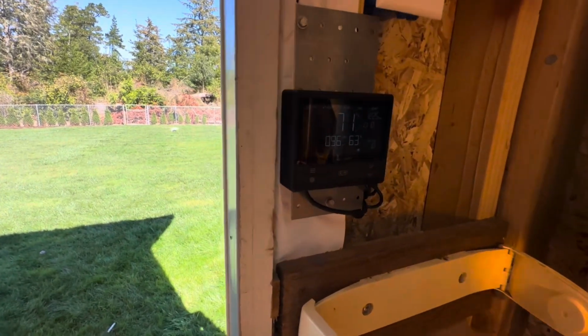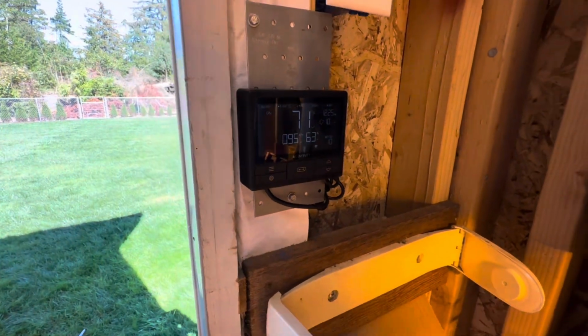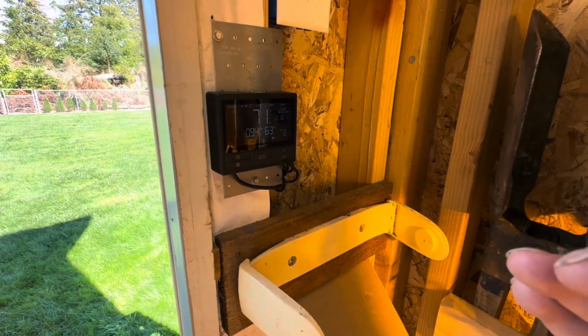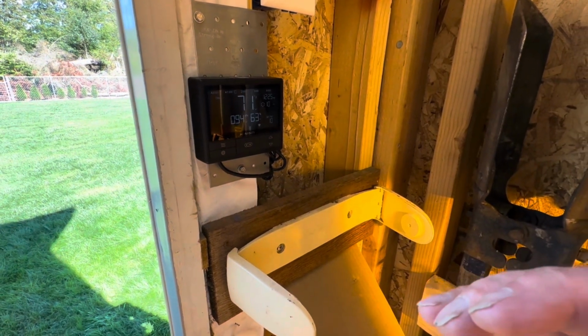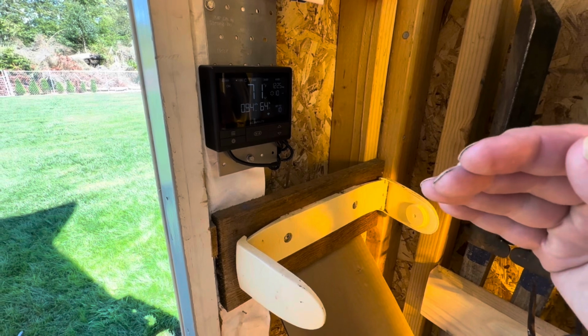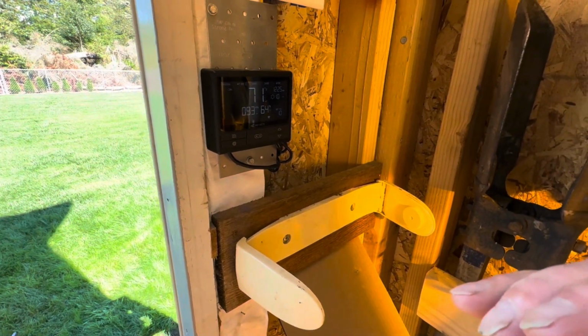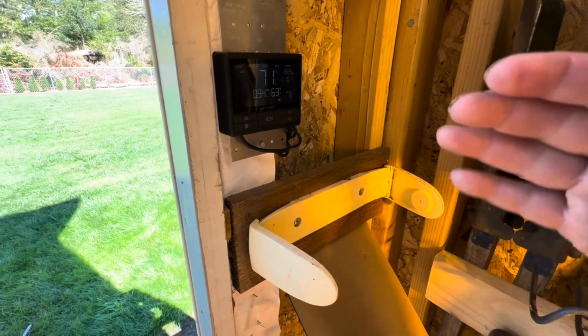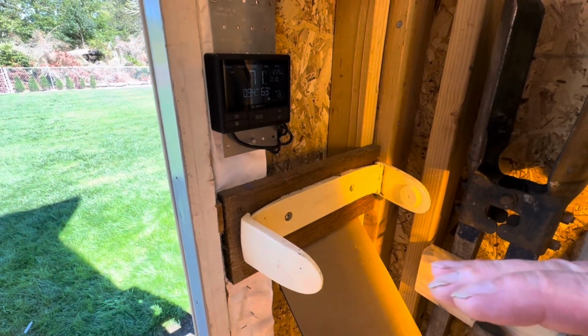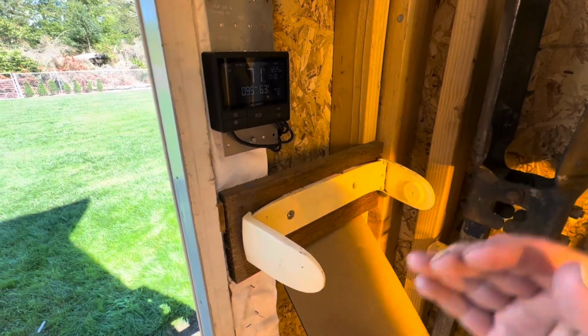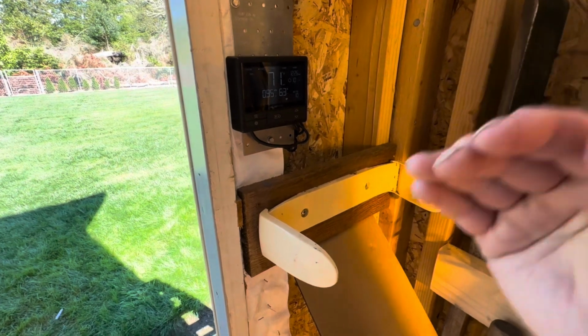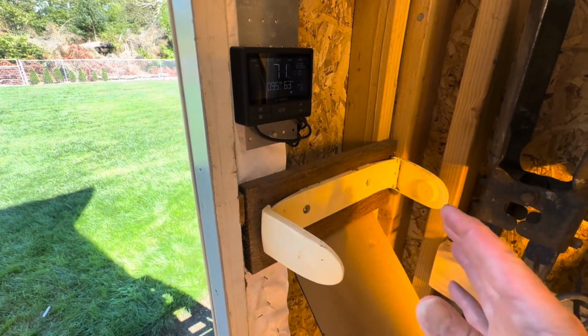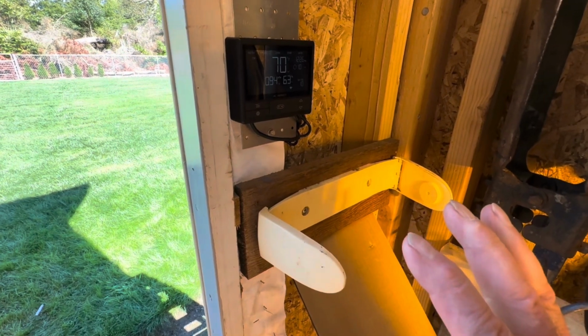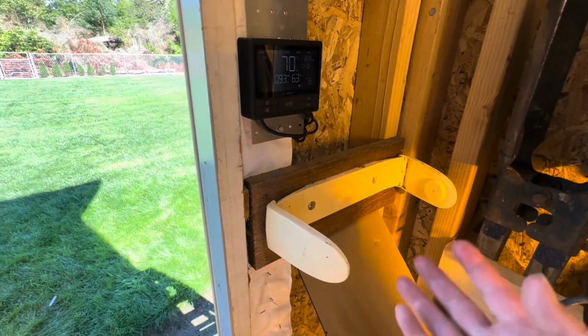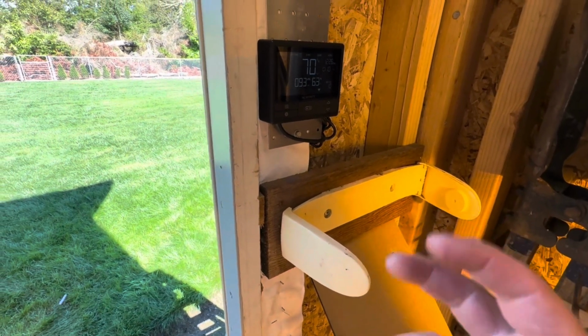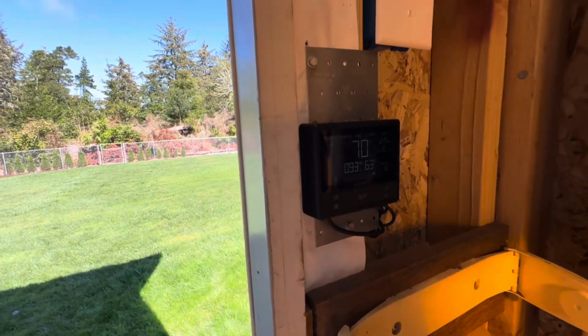As far as accuracy, the sweet thing about this is the flexibility. You can set high and low parameters. In other words, whether you need to cool or heat, dehumidify or humidify. You can set parameters to bring the temperature and humidity down, both, one or the other, or the temperature and humidity up, one or the other. You can do just temperature and leave the humidity out of it, or just humidity, or you can combine the two. And you can program in offsets.